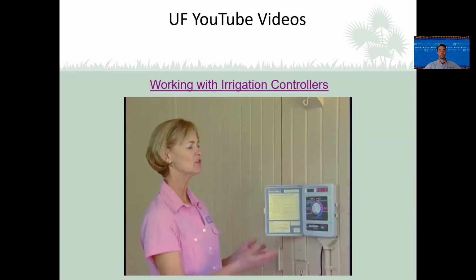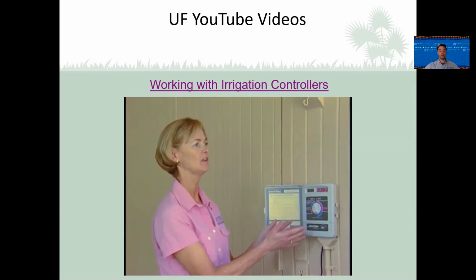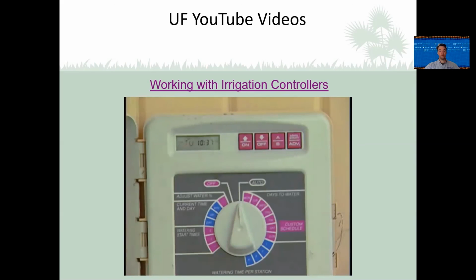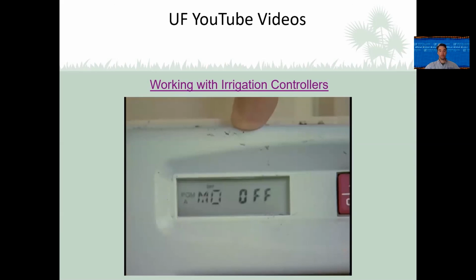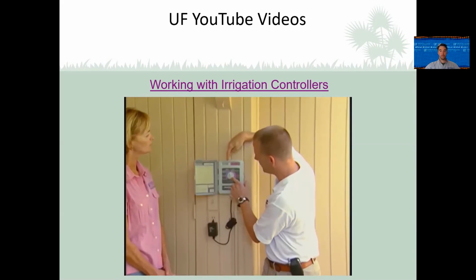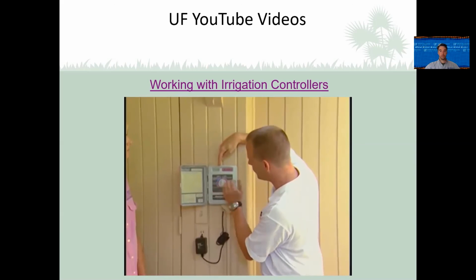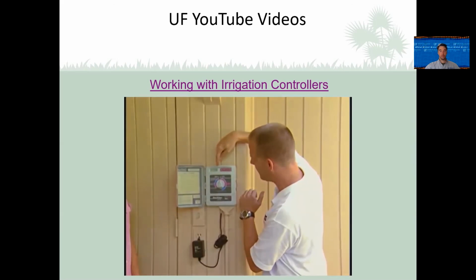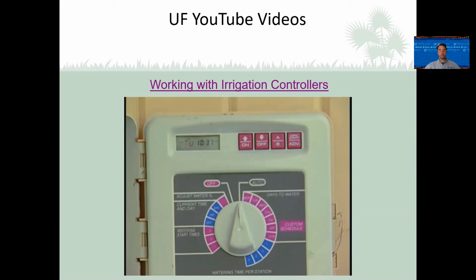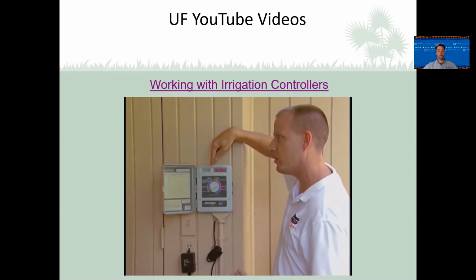So Michael, how would one change the frequency, or the number of days, with which they irrigate? You can see this controller here is pointed to off, and it tells you how it's operating because the last number blinks when it's off. When you turn it to an irrigation schedule, the time stays fixed. On this one, Monday says off, so it's not going to run on Monday. Tuesday it says on, Wednesday off, Thursday off, Friday on, and Saturday and Sunday are also off. So this one's set for 2 days a week on a custom schedule.